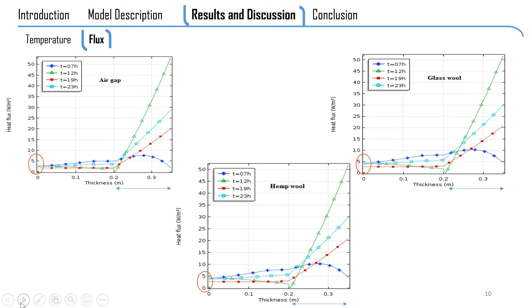At midday, the heat flux is higher compared to other times, and it reaches a value of 55 watts per meter square at the external side of the wall, and it decreases to 30 watts per meter square at 11 p.m. Then it gradually diminishes towards the inside with a value of 2.5 watts per meter square for the air gap, and it is nearly twice as high for the two other insulators with a value of 4 watts per meter square.